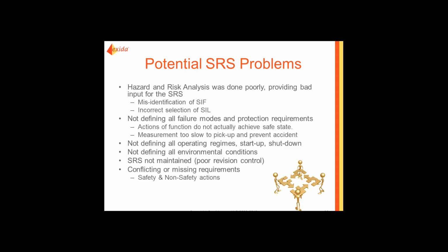in his SIS. And when I looked at it, he had control, non-safety control in the SIS. So what he was doing was adding to his cost, because the requirements for proof testing and maintenance on an SIS are much more stringent than they are on a BPCS.